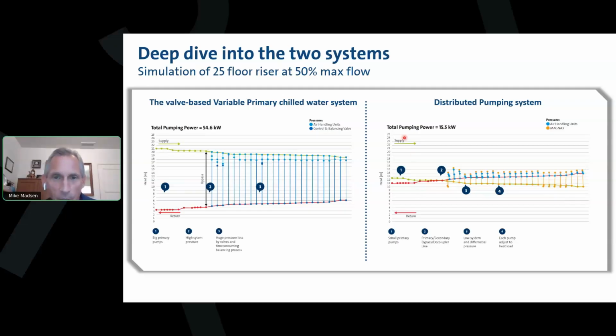So with the distributed pumping approach, you have 16 kilowatts. So you can see the tremendous energy savings opportunity here with distributed pumping. And it's a very, very easy retrofit. I know there's a lot of ESCOs on the call. This is a very easy retrofit to go in and convert a system from conventional control valves to distributed pumping.